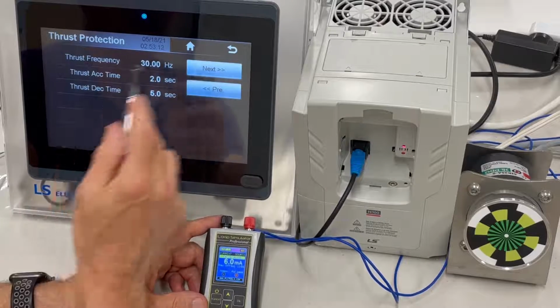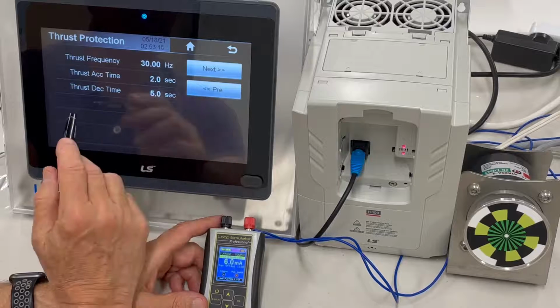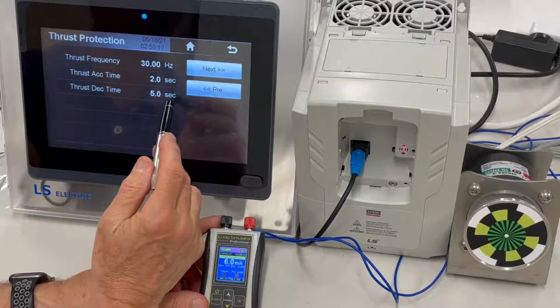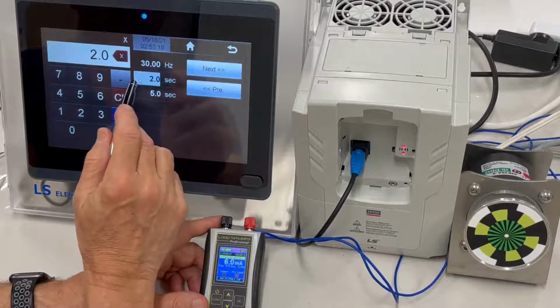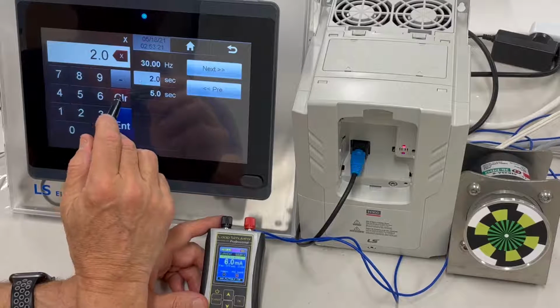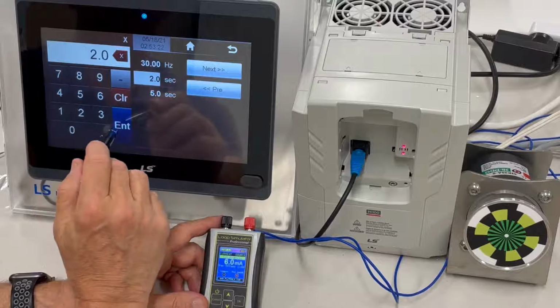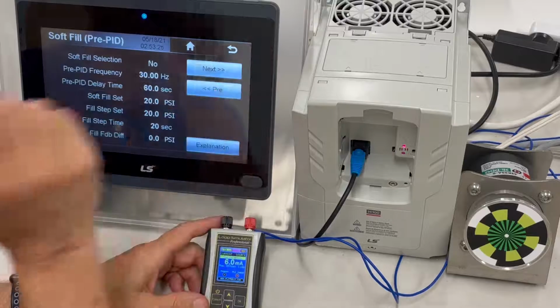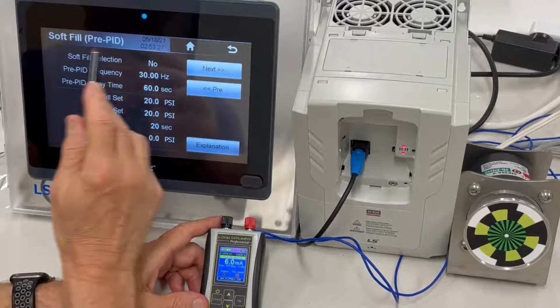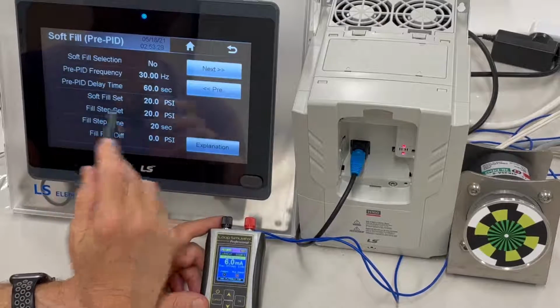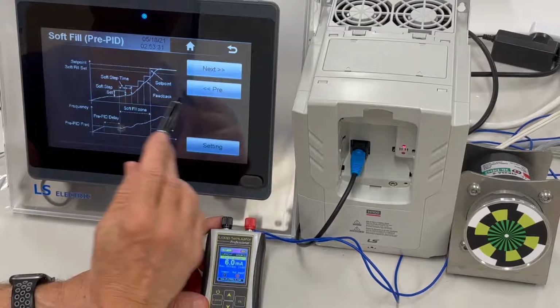Thrust bearing protection is at 30 Hertz. Thrust acceleration time is 2 seconds. Thrust decel times 5. All completely configurable, just as we said. And you should use the recommendation of your pump very easily to get that in there. Soft fill capabilities, if you need to know what that is, here's a quick graphic.